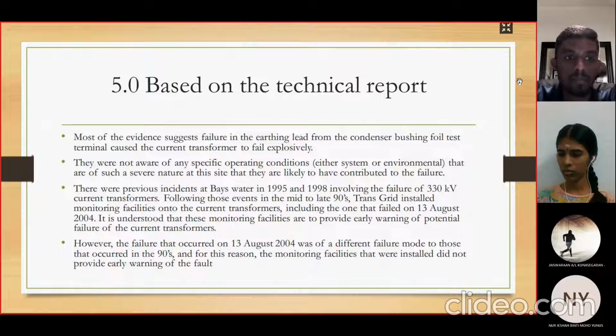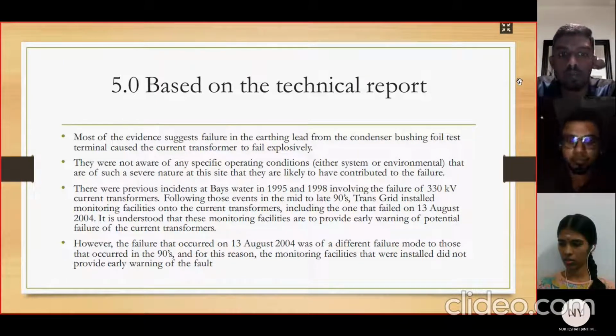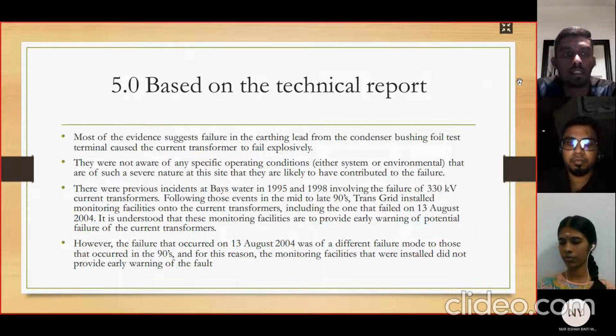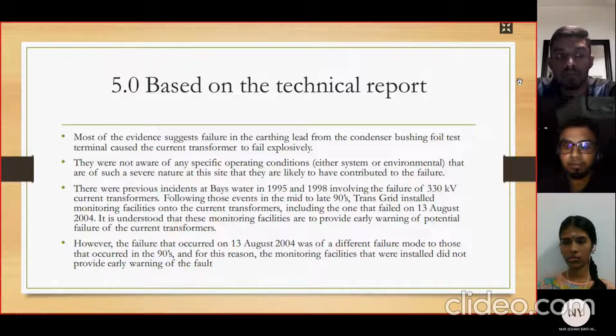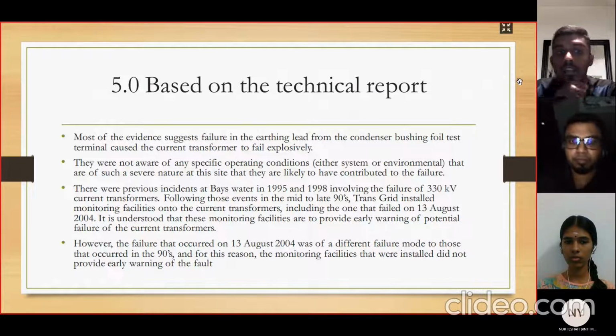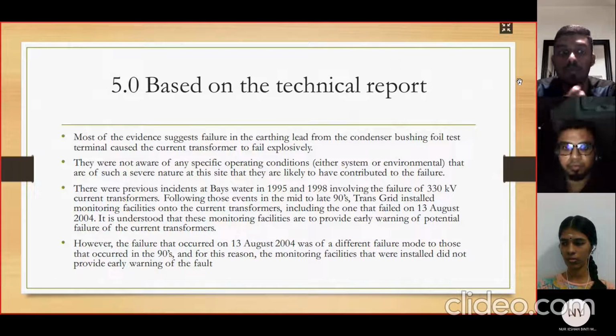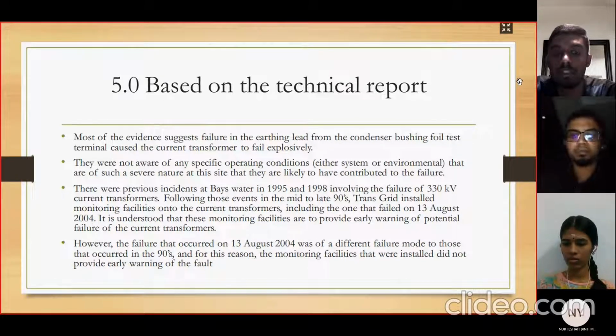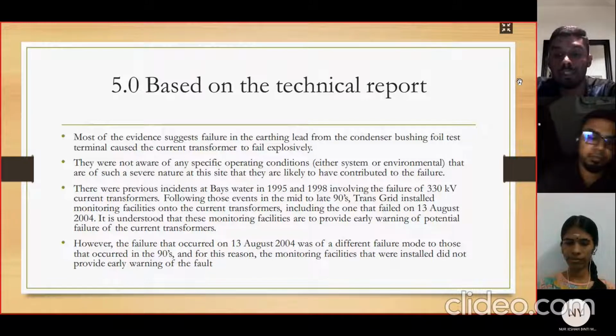Number three, there were previous incidents at Bayswater in 1995 and 1998 involving the failure of 330 kV current transformers. Following those events, in the mid to late 90s, Transgrid installed monitoring facilities onto the current transformers, including the one that failed on 13 August 2004. These monitoring facilities are understood to provide early warning of potential failure of the current transformers. However, the failure that occurred on 13 August 2004 was a different failure mode to those in the 90s, and for this reason the monitoring facilities did not provide early warning of the fault. So based on the technical report, this is what I have understood. Next slide.